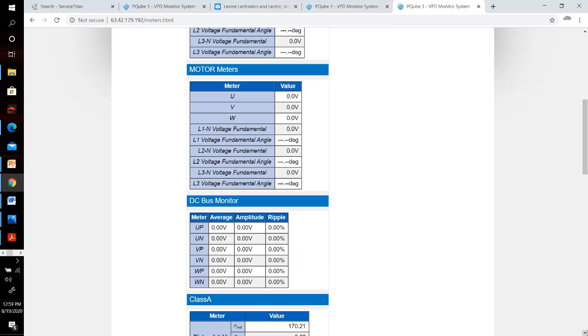So this is an example on my drive, give me a minute - they're putting 4160 volts on my drive and they're going to run it here so we can show you some of this. If we look at this, this is actually my DC bus on the Toshiba medium voltage drive. You can see at the moment it's off. Over here we'll see the ripple, the amplitude of the ripple that is riding on each DC bus, and this is actually my ripple ratio on each DC bus.